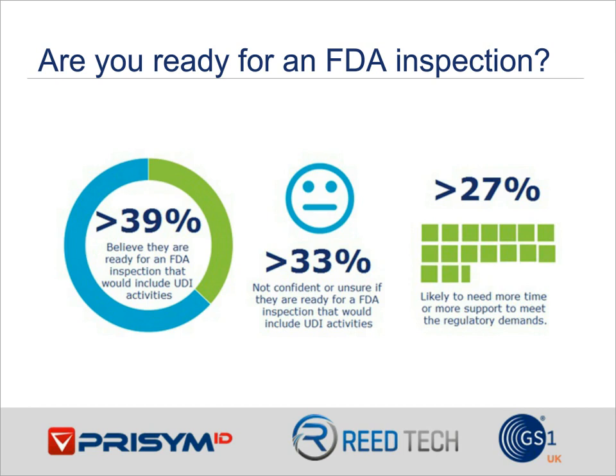Gary, what's your thought? Well, I was going to add a little bit about the reporting. Many times that is kind of an afterthought when you read through the final rule. It's one of the final sections. But UDI does pop up on your periodic reports, certainly in your quality system, some of your production tracking reports, certainly your MDR for adverse events. When you report an event and a UDI is available, you need to submit that.